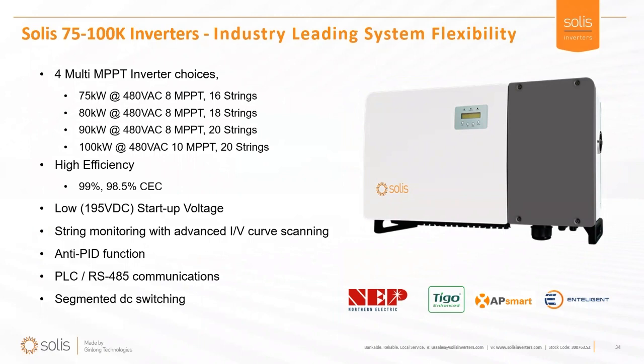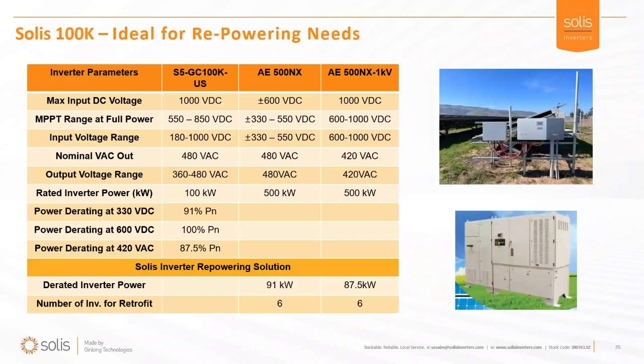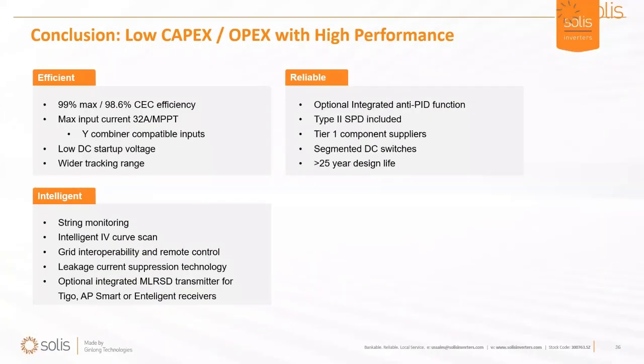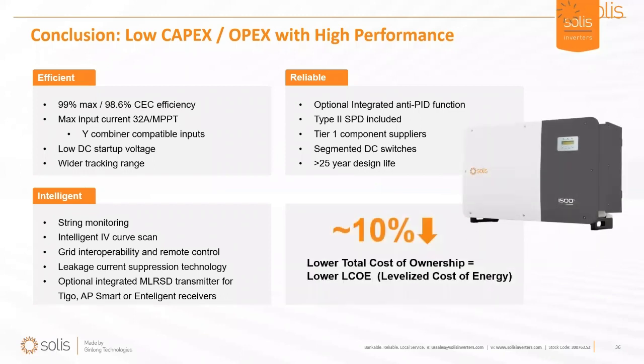It's got super low startup, and the capability to handle anywhere from 360 to 480 volts on the AC side, and a super wide full power operating range on the DC side to handle legacy PV arrays. We're seeing this used all over to replace older inverters that still have a great PV array and well-protected wiring. We can re-energize these systems with a new inverter, using new capabilities to communicate with it, better stabler equipment for better OpEx, and put new life into sites where the land, contracts, off-taker, or interconnection agreements are valuable. You can re-energize those projects with these new Solis inverters.